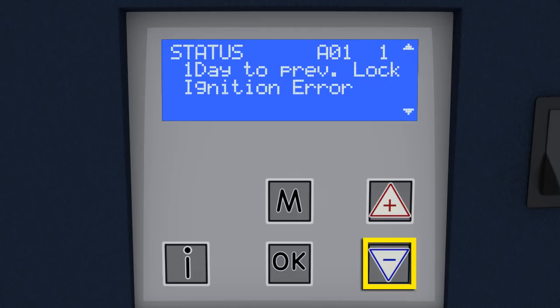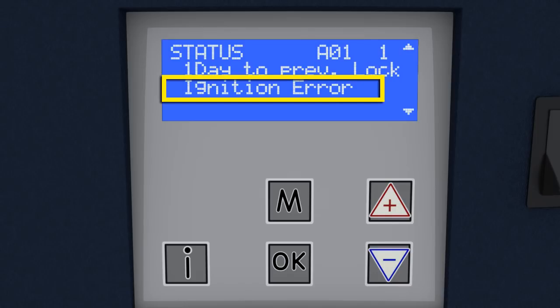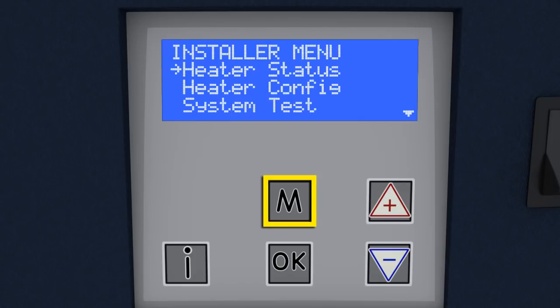Use the down arrow to advance to the final screen displaying lockout errors. The time interval between errors is listed in minutes, hours, days, and weeks as needed. To the right of the word status is the letter A, followed by the number of the error code. The error message is shown below the time interval. Press the M button to exit the status menus.